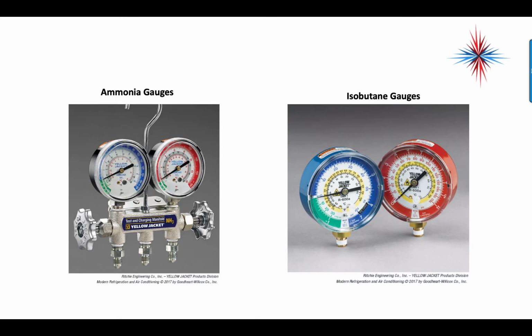Okay, so again, we have ammonia gauges and we have the isobutane gauges, which is for the hydrocarbons. Please note that ammonia is an inhalation danger. You cannot breathe it in. Propane obviously is a flammable situation. Do not light a match near this and don't have a spark.